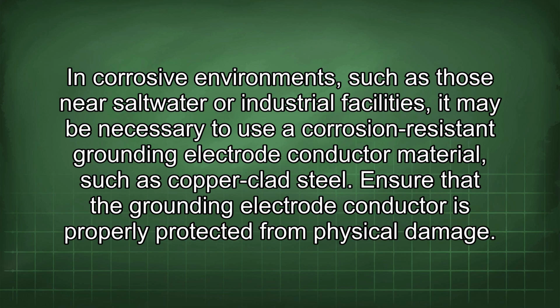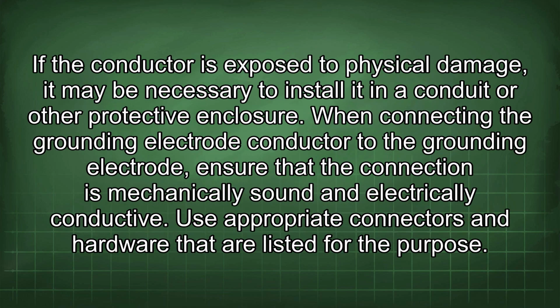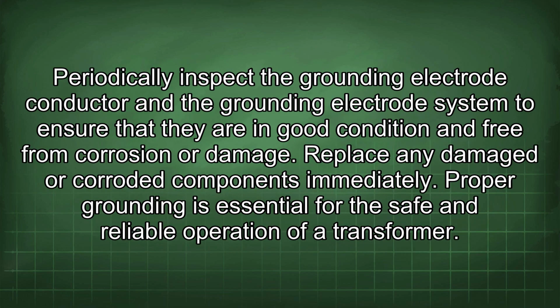Ensure that the grounding electrode conductor is properly protected from physical damage. If the conductor is exposed to physical damage, it may be necessary to install it in a conduit or other protective enclosure. When connecting the grounding electrode conductor to the grounding electrode, ensure that the connection is mechanically sound and electrically conductive. Use appropriate connectors and hardware that are listed for the purpose. Periodically inspect the grounding electrode conductor and the grounding electrode system to ensure that they are in good condition and free from corrosion or damage. Replace any damaged or corroded components immediately.